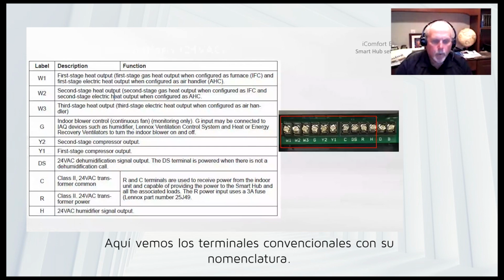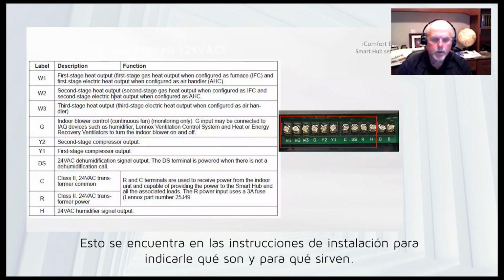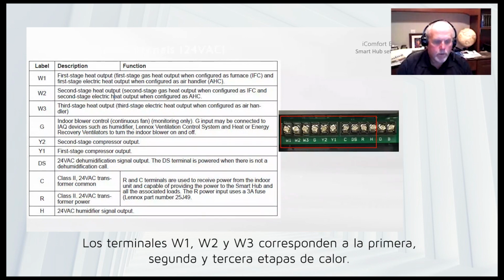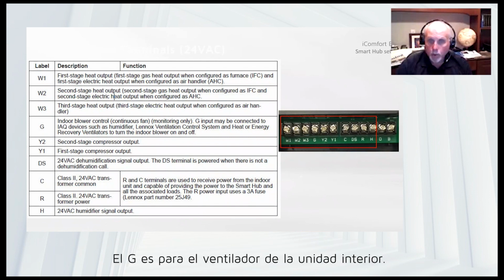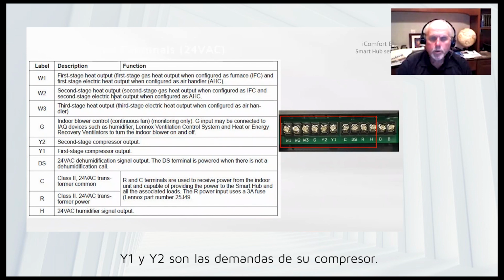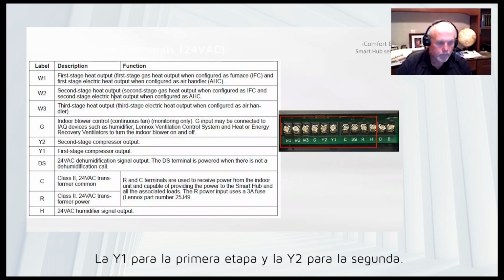So here we are with our conventional terminals. Here is our nomenclature. This is in the installation instructions to tell you what they are and what they're for. We can go down the line. W1, W2, W3 is your first, second, and third stage heat. G is your indoor blower. Y1, Y2 is your compressor demands. Y1 first stage, Y2 second stage.